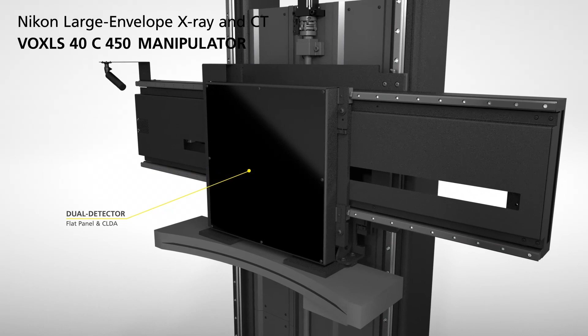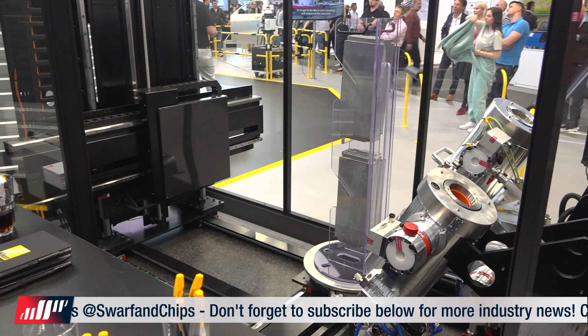It's also good for those honeycomb structures and little carbon fiber walls inside automotive parts, and they're used a lot in F1 as well. Now, what Nikon love about this is the fact that it's all a complete cabinet. It's all one piece, and it weighs 20 tons, believe it or not. Because of the lead lining, that means it's completely protected. It means it's perfectly safe. While it's running, Andrew was telling me you could lean against it for a whole year. While it's running, you'd be absolutely fine.